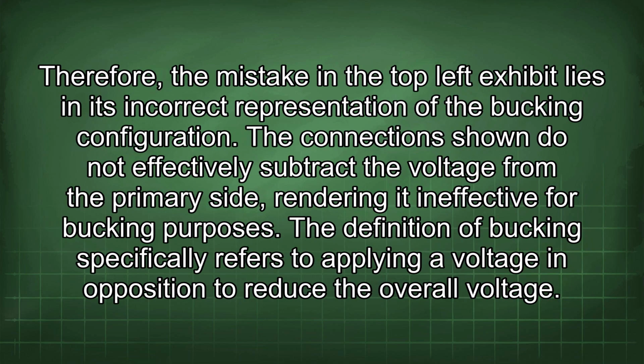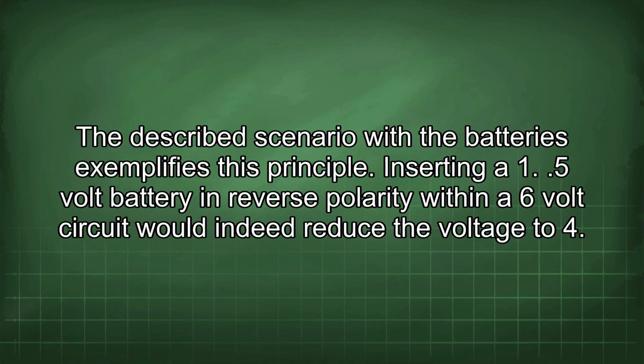Therefore, the mistake in the top left exhibit lies in its incorrect representation of the bucking configuration. The connections shown do not effectively subtract the voltage from the primary side, rendering it ineffective for bucking purposes. The definition of bucking specifically refers to applying a voltage in opposition to reduce the overall voltage. The described scenario with the batteries exemplifies this principle.